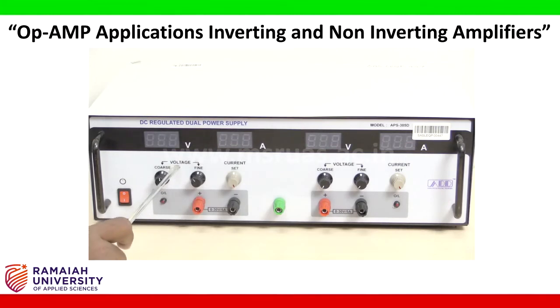So in the voltage tuner we have two main categories. One is coarse tune and one is a fine tune. If you want to tune your voltage to maximum level in maximum numbers, that will be used by coarse tuner. If you want to tune the voltage in the minimum level, that will be chosen with a fine tuner terminal. So if you want to set your current, that will be based upon the application, so you can set by using this current set terminal.